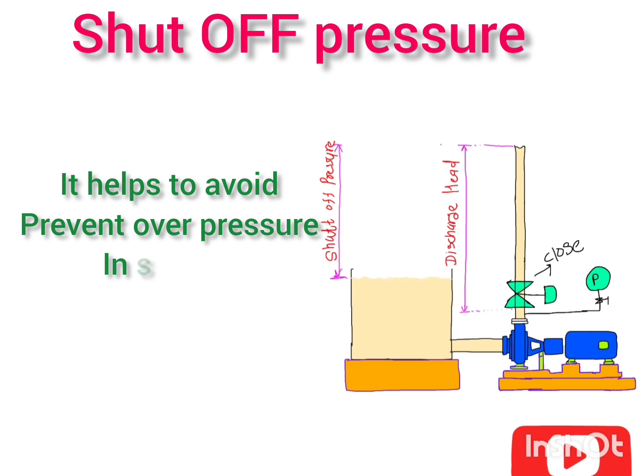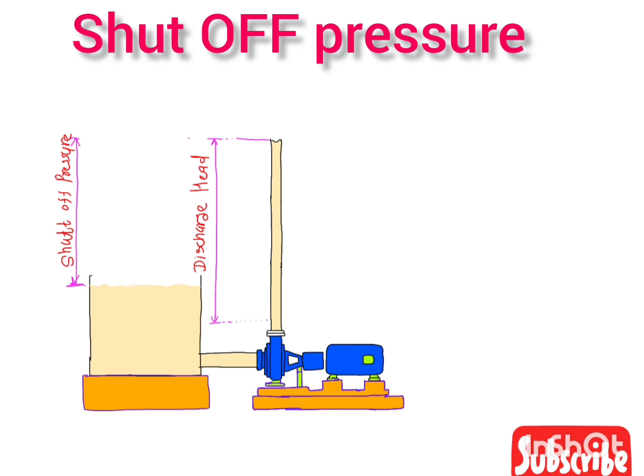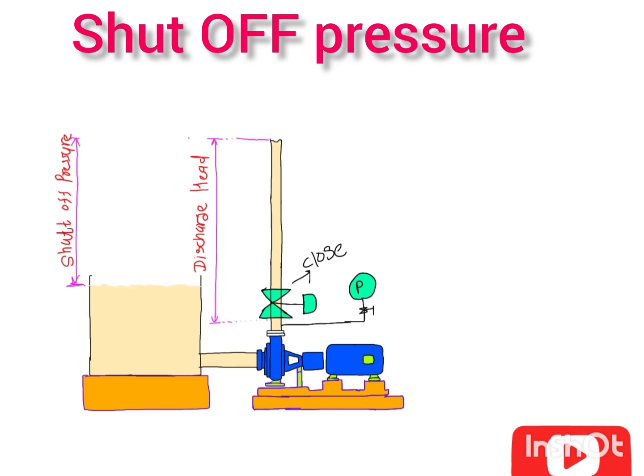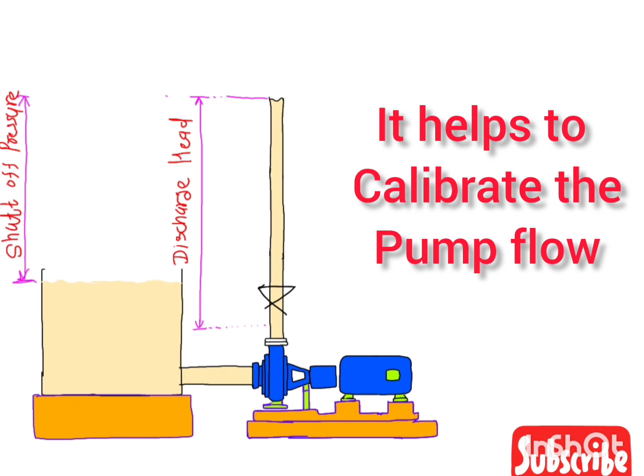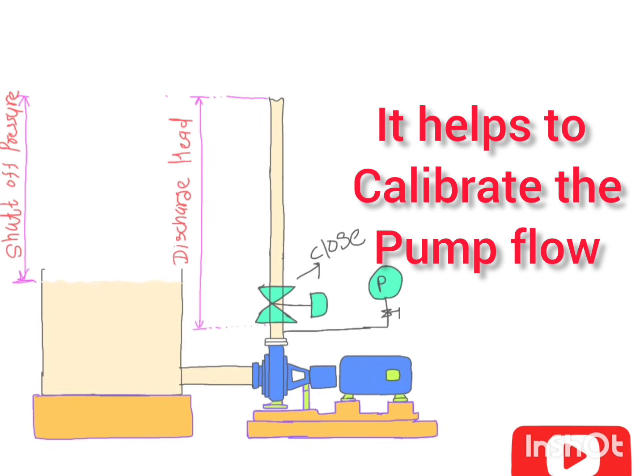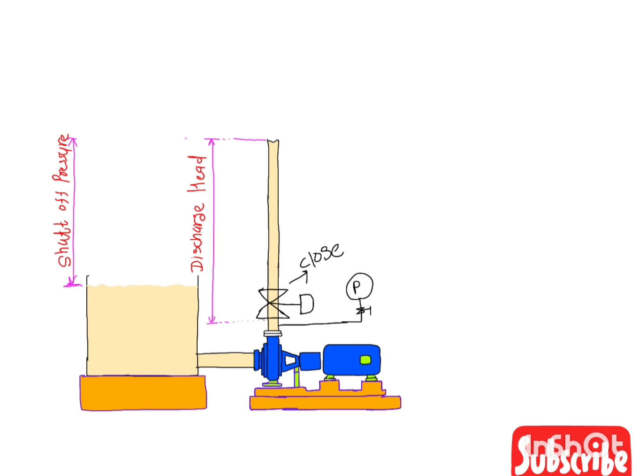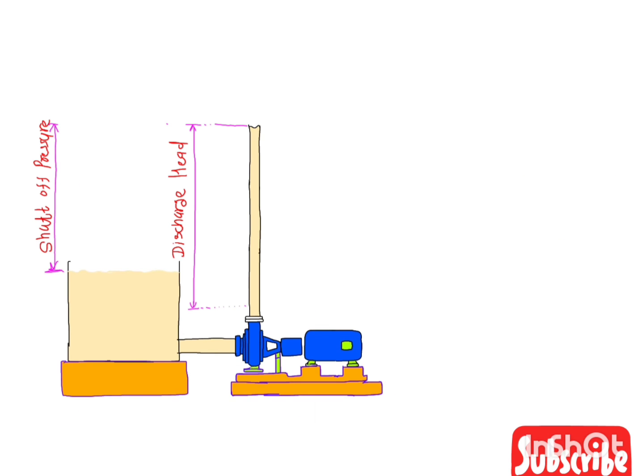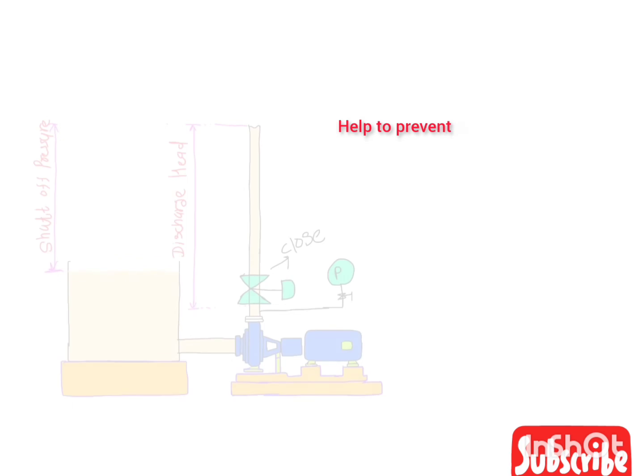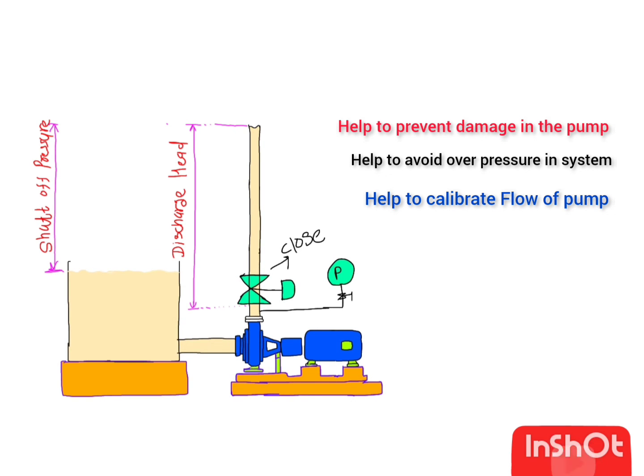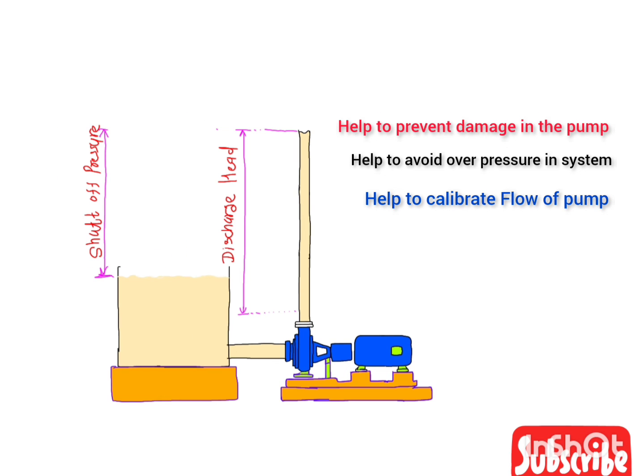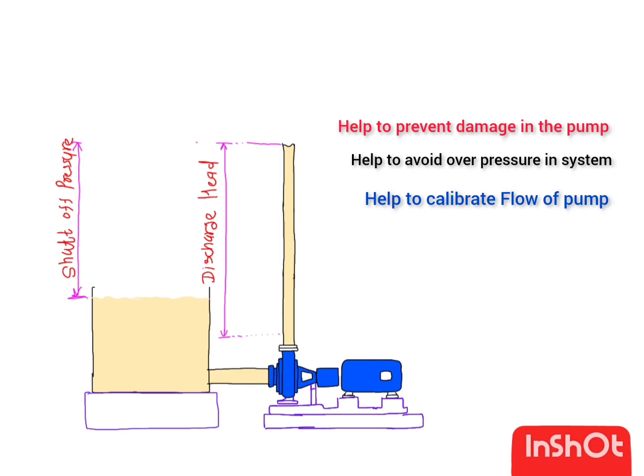The third benefit is that shut-off pressure helps in systems that require precise flow control, such as chemical processing or water treatment. It is used to calibrate the pump and ensure it delivers the desired flow rate at a given pressure. So the three main benefits are: preventing pump damage, preventing overpressure, and ensuring accurate flow.